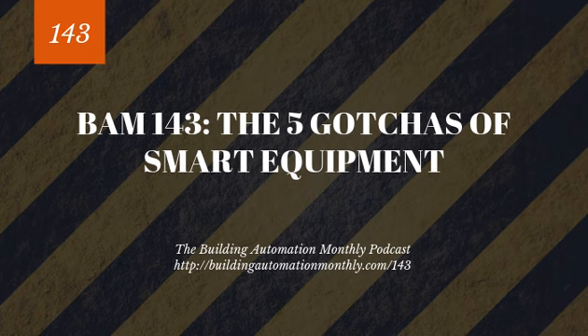There's nothing that sucks more than going and doing commissioning. So remember, in a project, we create our submittals, get approved, we have our installer come and install, we pull the system in. When we're talking about smart equipment, our installer is most likely going to run BACnet MSTP or BACnet IP to the smart equipment, and then we are going to map the equipment in, which we'll talk more about in a second. We're going to map that in to our BAS.